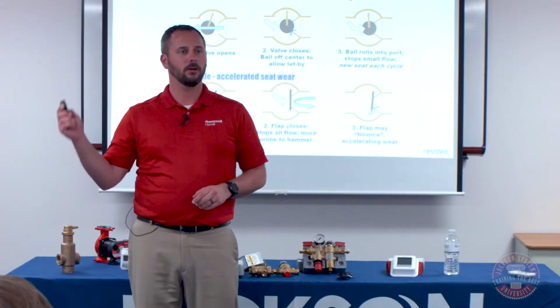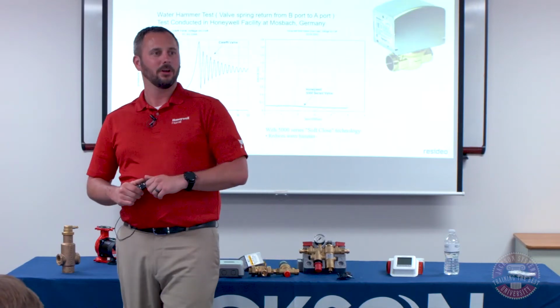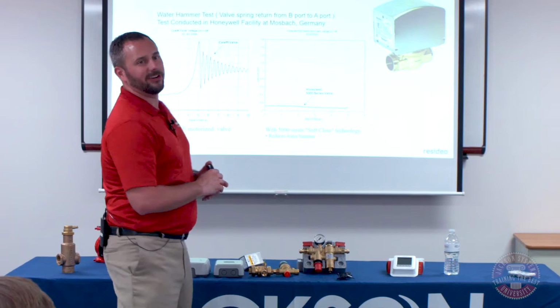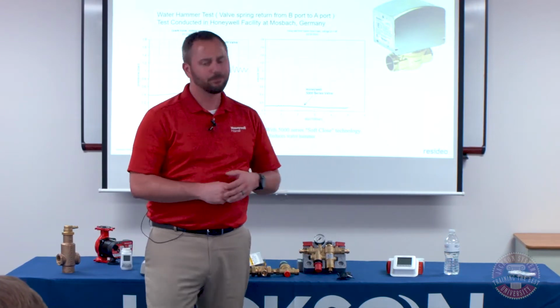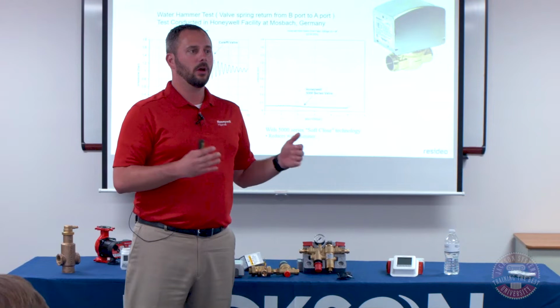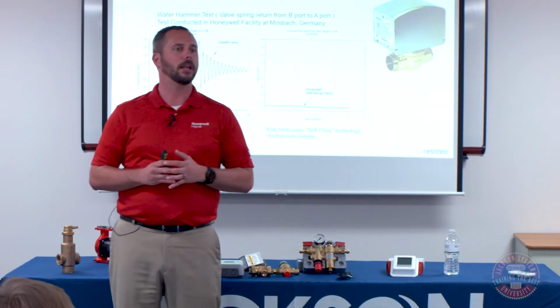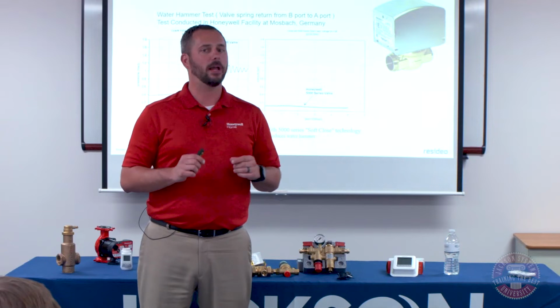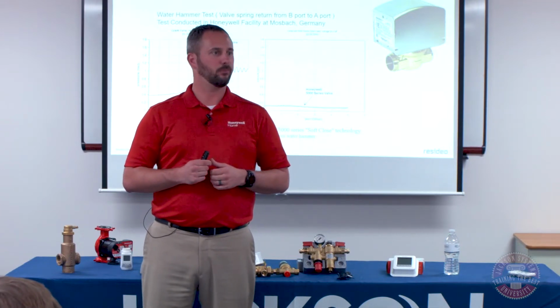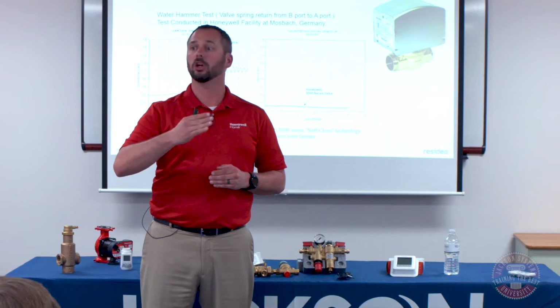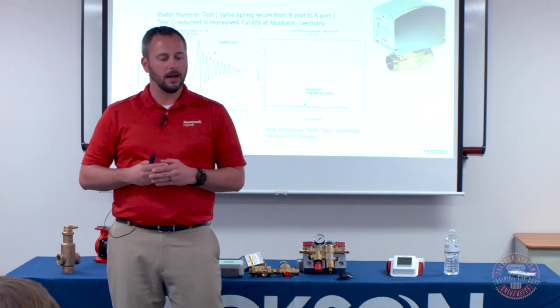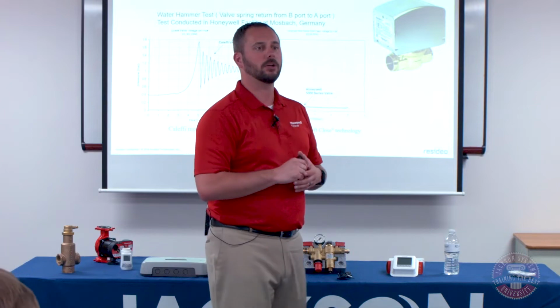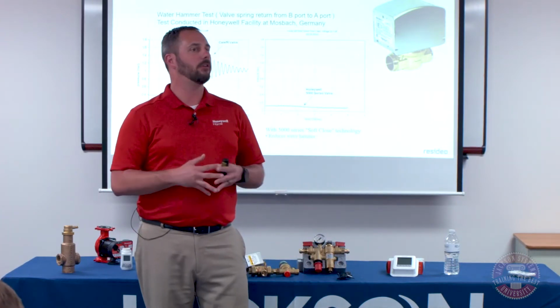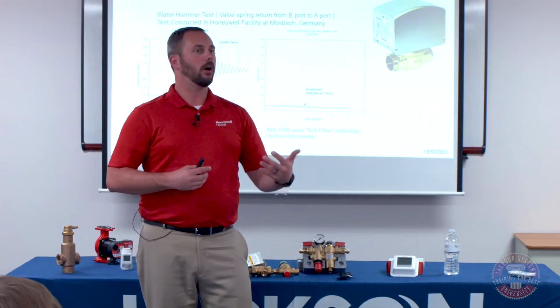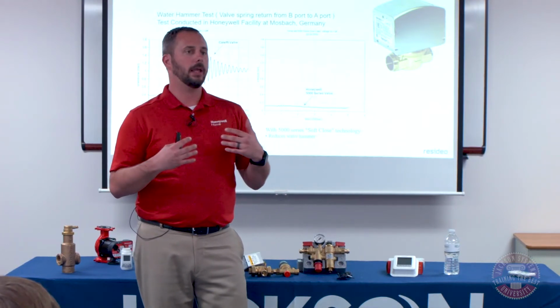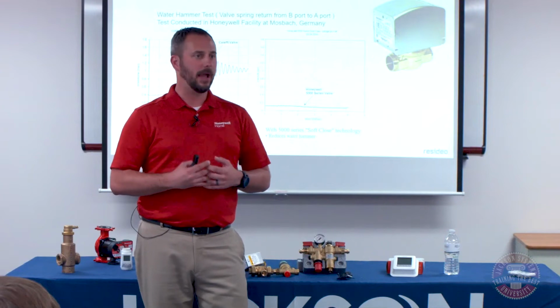With that being said, we do have another series of valves. We have a 5000 series. We got real creative with the numbering system here. Our 1000 is our basic one. Our 5000 has a slightly different valve body, but really the beauty of the 5000 is the power head. We've put an extra spring in there, so it's a much more controlled, slower closing operation. It's also more consistent because those springs are much heavier duty. So if you have a job site with one of our valve bodies, you can go in and put in a 5000 series power head.